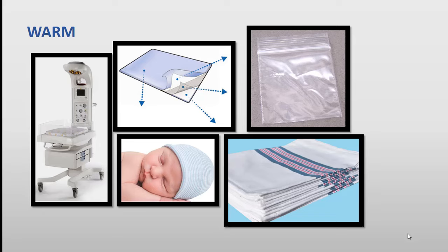Babies are very sensitive to heat, and because of the thinness of their skin and the translucence of their skin, the heat production really needs to be monitored closely, and having the safety mechanism within the giraffe regulating the heat according to the baby's temperature is the safest and best practice to follow.